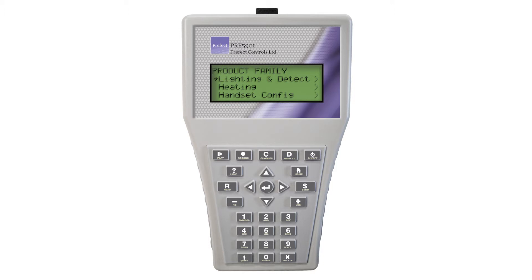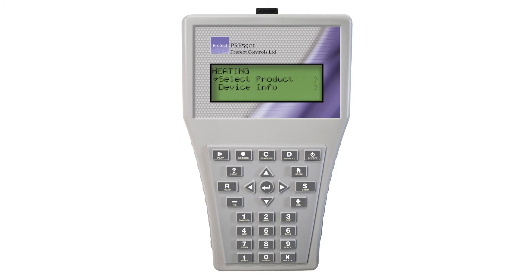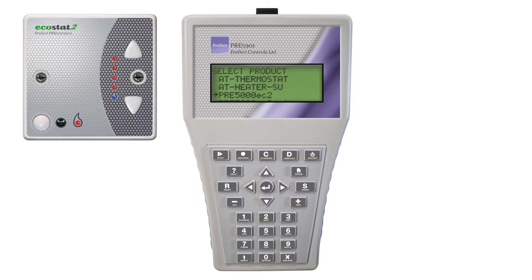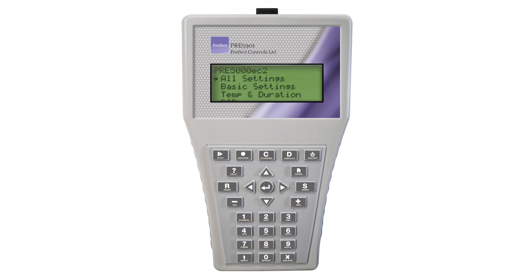Choose the family of products you wish to program. For this demonstration, we are programming a heating thermostat. Use the down button to scroll to heating and press the return button. The first option is 'select product' — press the return button to choose this option. The range of products will be displayed. Use the down button to move the arrow to the correct device. In this case, we are programming a PRE5000 EC2 series product. Press the right arrow again. Here you have a list of options to make navigation of settings easier. All settings is the master list and contains the times, temperatures, and all configuration settings for the Ecostat 2 range.